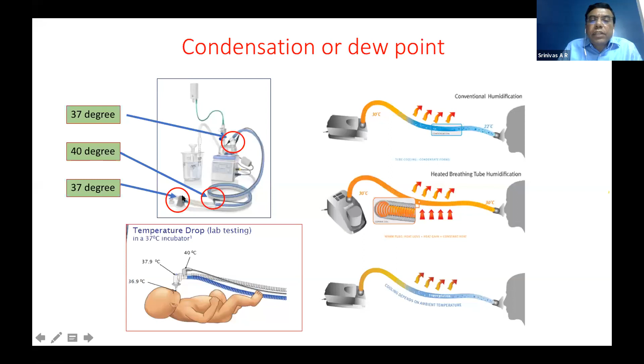Why has this been done? This is with a purpose. Again, when the air travels from this point through the interface to the baby, there is a drop in temperature because there is no heated wire here. So the temperature goes back to 37 degrees, and that's where it has 100% relative humidity, which the nose of babies requires. So this is the picture showing the different temperatures in different areas. So this baby requires 37 degree air with 100% relative humidity.